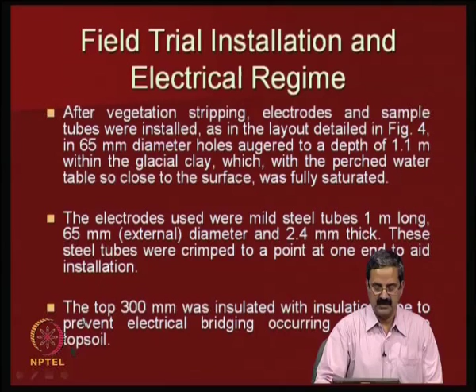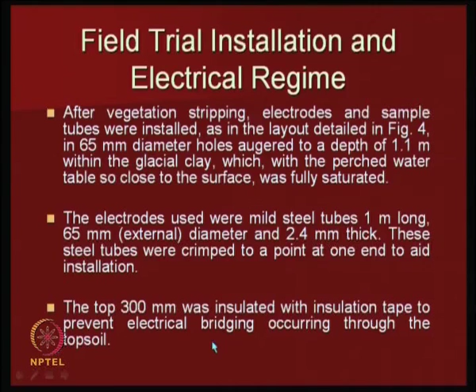with the perched water table close to the ground surface, fully saturated. So, the water table is close to the ground surface. The electrodes used were mild steel tubes 1 meter long, 65 mm external diameter and 2.4 mm thick. These were crimped to a point at the end to aid installation, like you can make that particular end a little better pointed, so that it is easy for installation. The top 300 mm was insulated to prevent electrical bridging, okay, that is important.